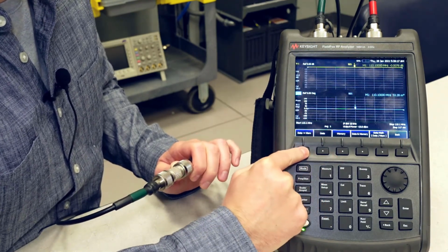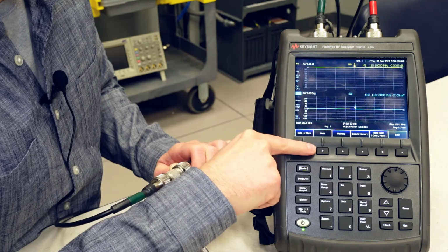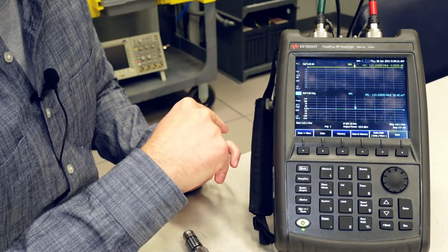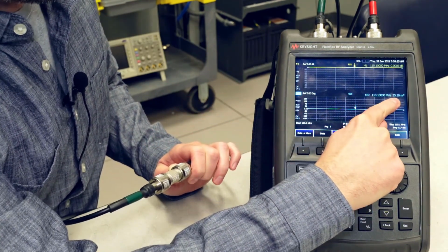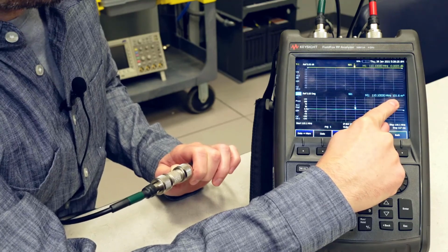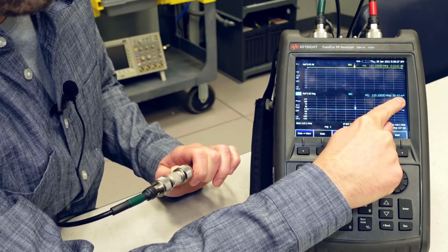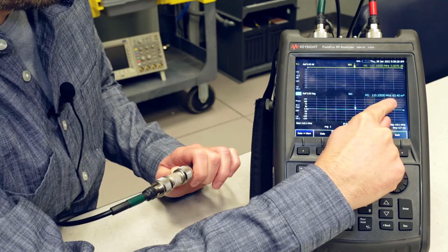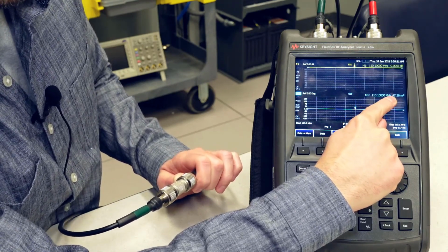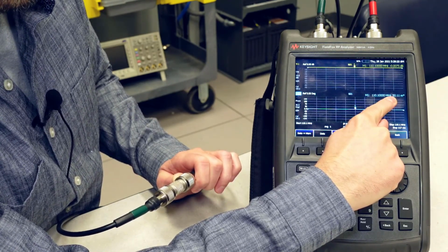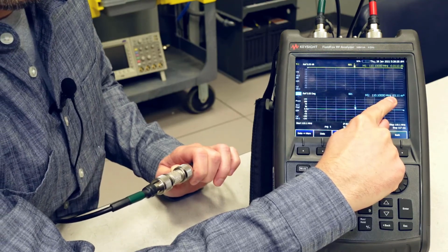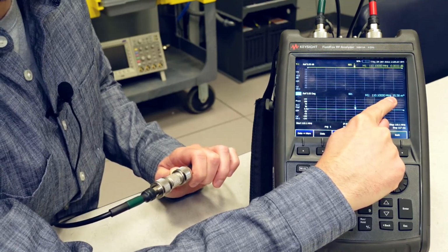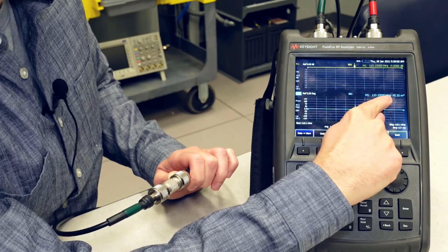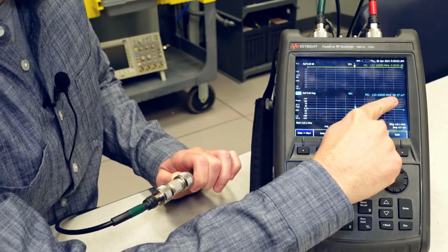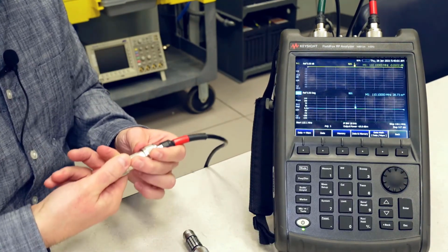If you wanted to, you could hit data to memory one more time, just to ensure that it is zeroed out. The reading up here is fluctuating quite a bit, but you have to realize that it's in milli-degrees. It's at 50 milli-degrees. In reality, that's 0.05 degrees, which is pretty much 0. So now we're ready to insert the device under test.